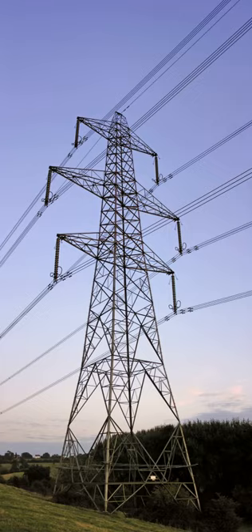Before transmission towers are even erected, prototype towers are tested at tower testing stations. There are a variety of ways they can then be assembled and erected. They can be assembled horizontally on the ground and erected by push-pull cable. This method is rarely used because of the large assembly area needed.